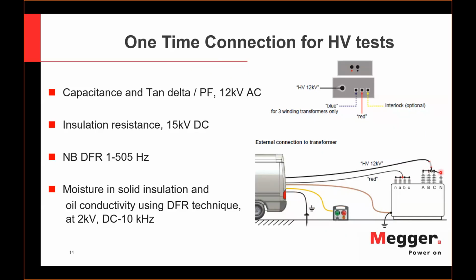So you short all three phases plus neutral together and connect your HV cable, red cable, on the high voltage side, on the low voltage side, and if you happen to have a tertiary on your transformer, you even take a blue lead and also connect it to the tertiary at the same time. You observe the lights, whether it's safe or not safe to touch leads or interconnect. And you connect the other end of the drums or cable reels to the switch box. So as I said, one-time connection for HV tests.